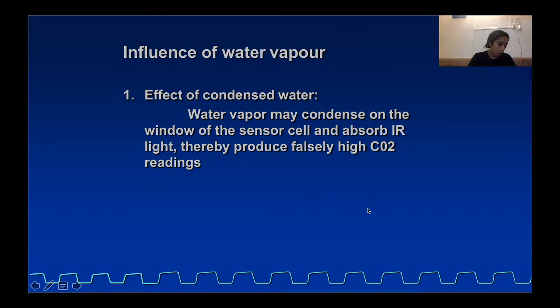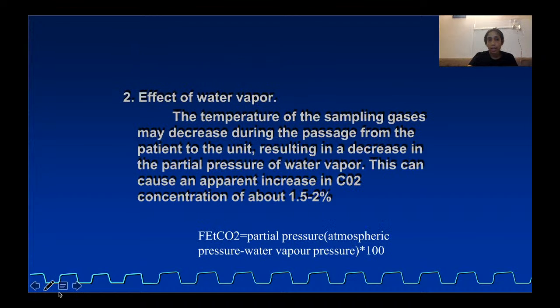Then the influence of water vapor, the effect of condensed water vapor. Water vapor may condense on the window of the sensor cell, which we already discussed, and absorb infrared light, thereby producing a false high carbon dioxide reading. The temperature of the sampling gases may decrease during the passage from the patient to the unit, resulting in a decrease in partial pressure of water vapor. This can cause an increase in carbon dioxide by about 1.5 to 2%.